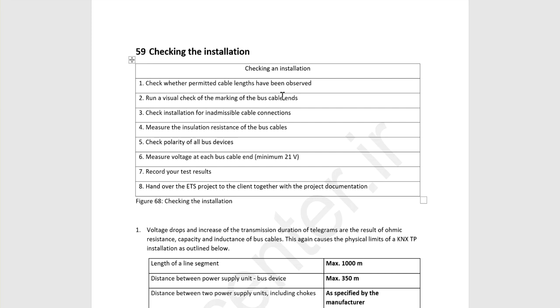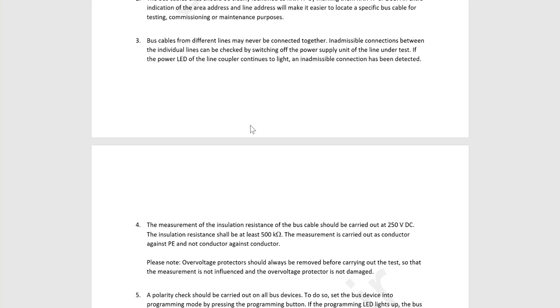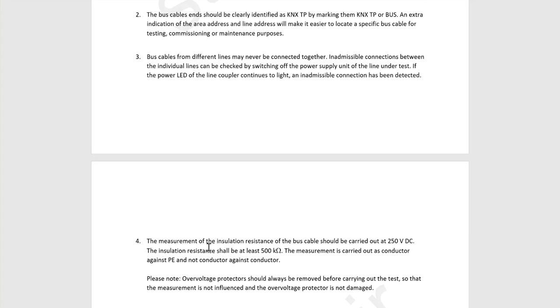Okay, this is something new I'm going to tell you. For a regular project we do not need it, but if you, for example, connect two buildings with the KNX connector and you don't have a connection, maybe you can use the insulation resistance. And what is the insulation resistance? In insulation resistance, you apply 250 volt DC and measure the insulation, and you should have 500 kilo ohm. The measurement is carried out as conductor against PE, and not conductor against conductor. I mean, you should measure the insulation resistance between the red wire and the earth and the black wire and the earth. It has special tools, this insulation resistance, and you should use that.